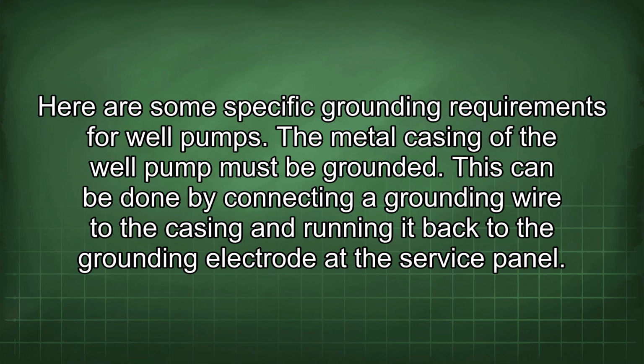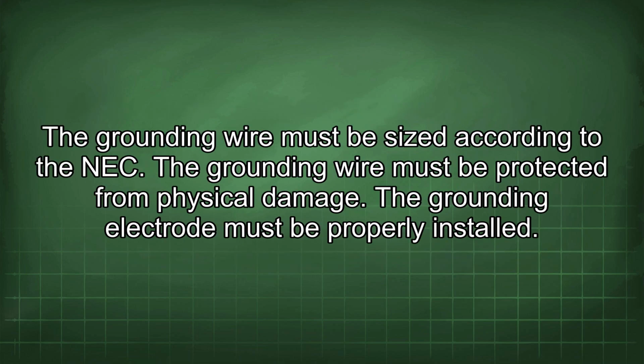Here are some specific grounding requirements for well pumps. The metal casing of the well pump must be grounded. This can be done by connecting a grounding wire to the casing and running it back to the grounding electrode at the service panel. The grounding wire must be sized according to the NEC. The grounding wire must be protected from physical damage. The grounding electrode must be properly installed.